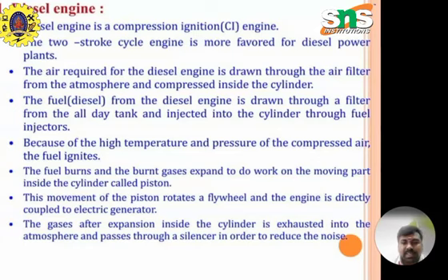Because of the high temperature and pressure of the compressed air, the fuel ignites. The fuel burns and the gases expand to do work on the moving part inside the cylinder. It is called the piston. This movement of the piston rotates the flywheel and the engine is directly coupled to the electric generator. The gases after expansion inside the cylinder are exhausted into the atmosphere and pass through the silencer in order to reduce the noise. This is the working of a typical diesel engine.